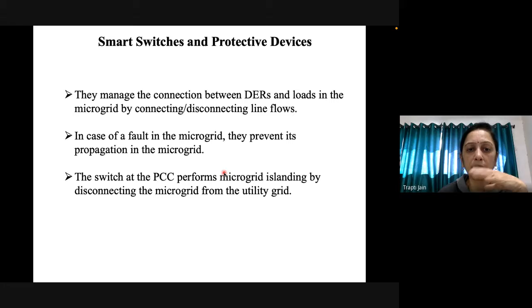Then there are smart switches and protective devices. These protective devices are required in the system to identify faults and prevent their propagation in the microgrid. These devices and smart switches manage the connection between DERs and loads in the microgrid - they disconnect and connect the line flows. The switch at the PCC performs microgrid islanding by disconnecting the microgrid from the utility grid.